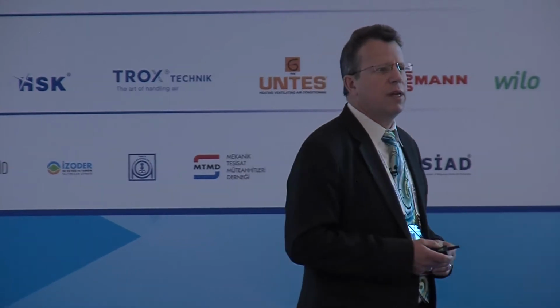If I put these compressors on an axis for capacity, meaning cooling capacity, from very small like a domestic refrigerator freezer, to very, very large air conditioning in large commercial buildings, you see roughly an application range for these 5 dominant compressor types. Recips probably have the largest application range, from very small fractional capacities up to 200 kilowatts using multiple machines, multiple pistons in parallel.